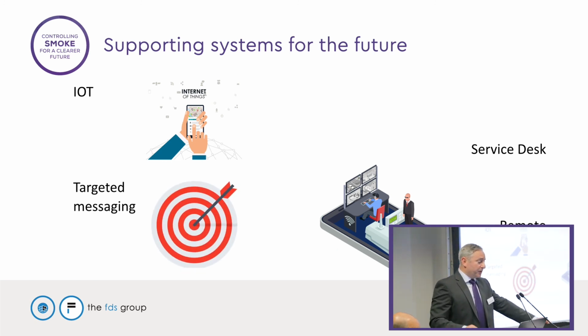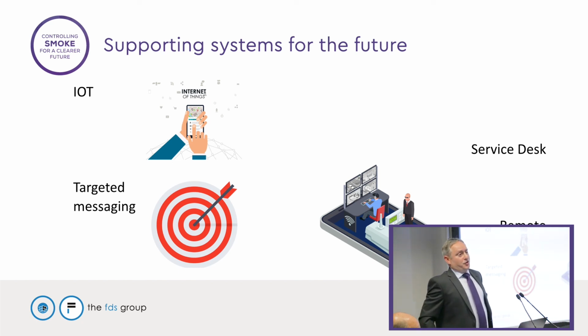We can also look at things like targeted messaging. So this would be where if a system generates a fault, maybe you don't need to tell everyone in the building that there's a fault on the system. Maybe you need to tell the engineer so we can go and fix it. Conversely, if there's a fire alarm, you probably don't need to tell the engineer there's been a fire alarm. You probably need to tell the concierge or the premises management. So we could start to look at how we provide the right information to the right people at the right time.